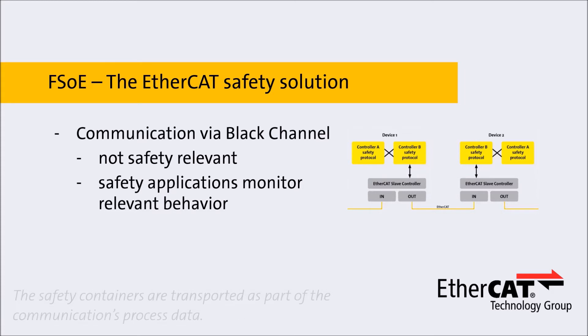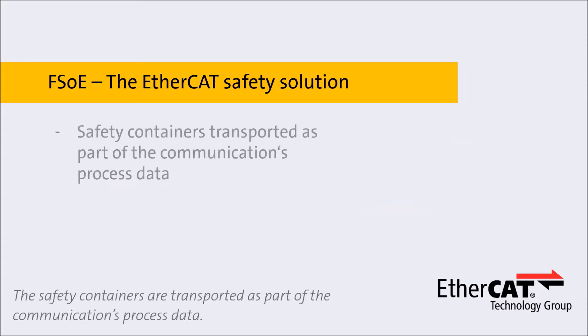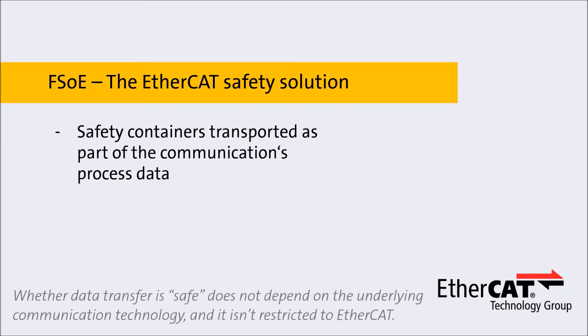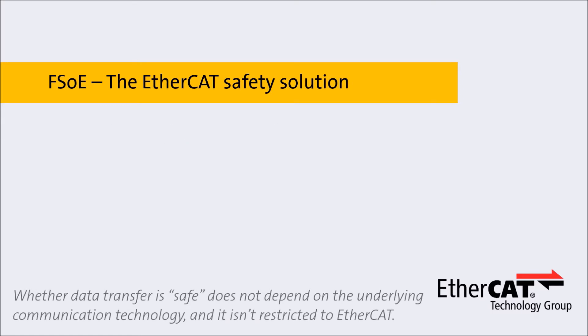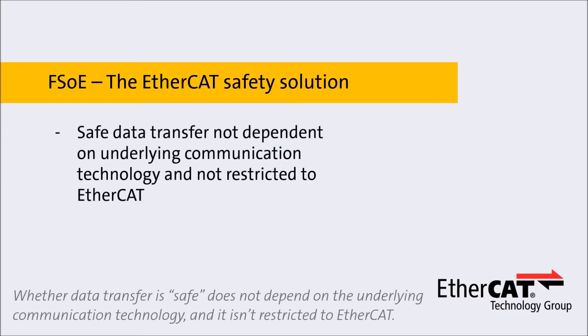The safety containers are transported as part of the communications process data. Whether data transfer is safe does not depend on the underlying communication technology and it isn't restricted to EtherCAT.